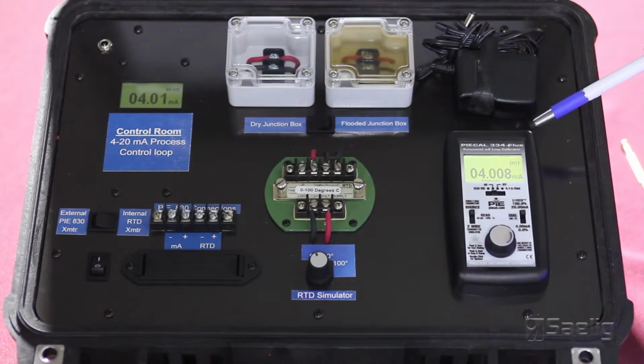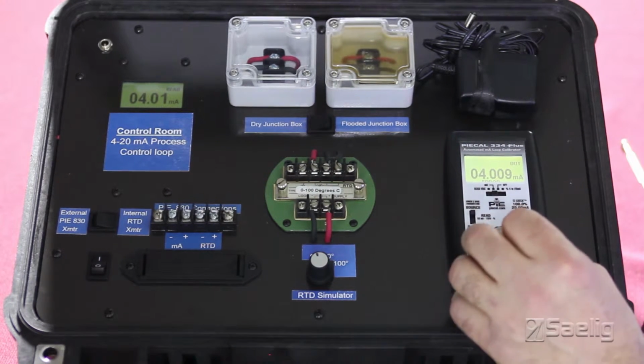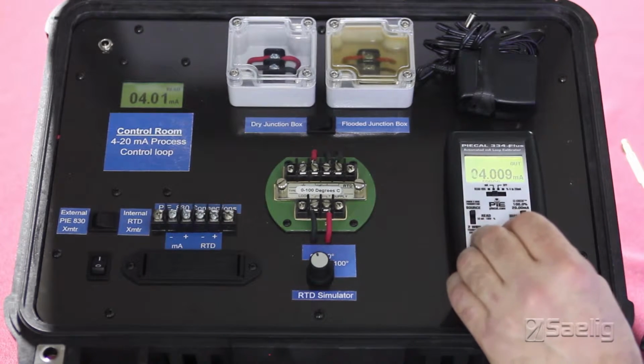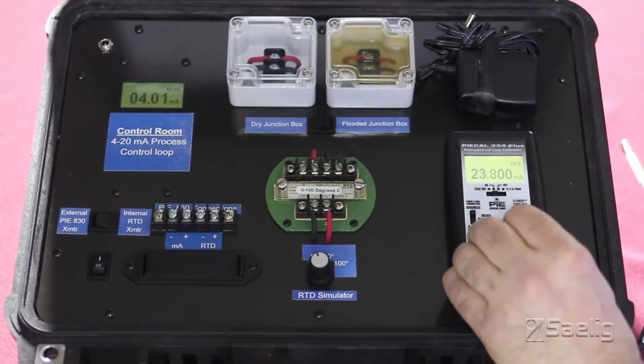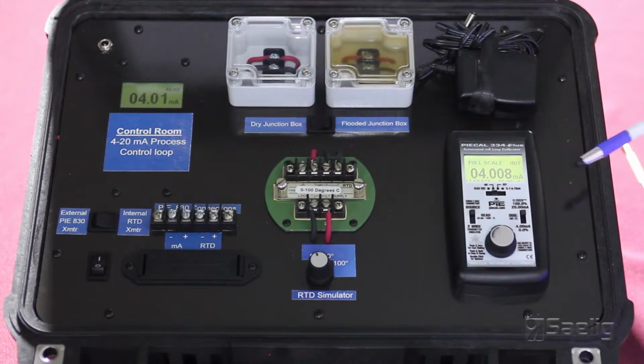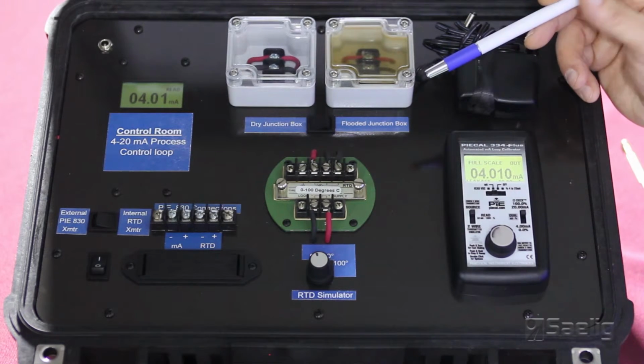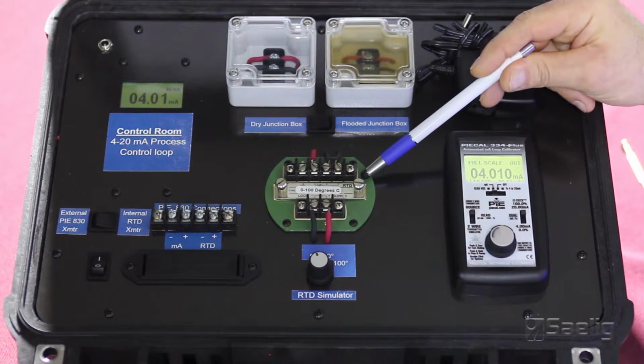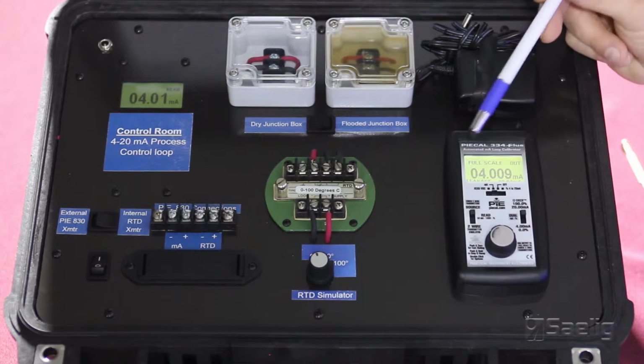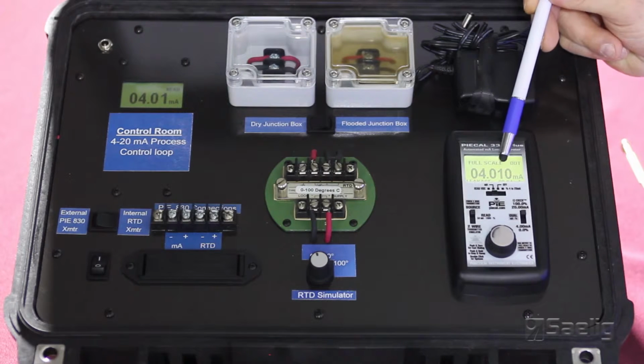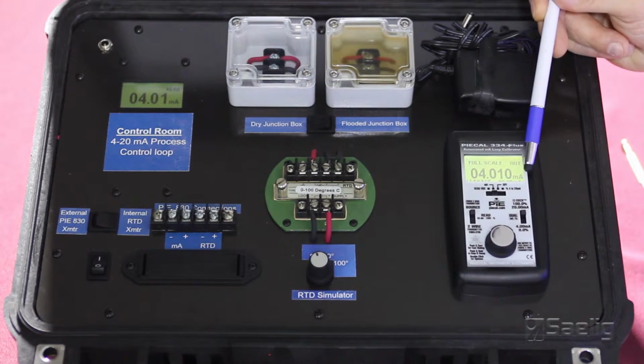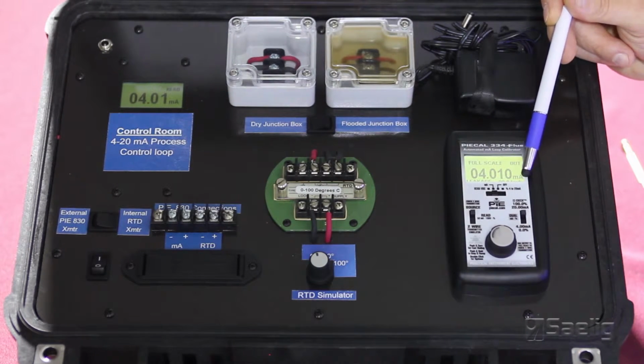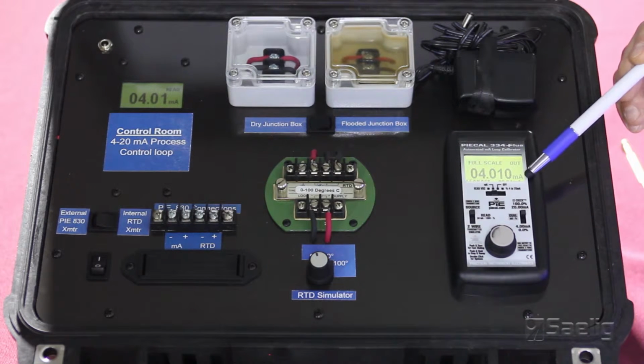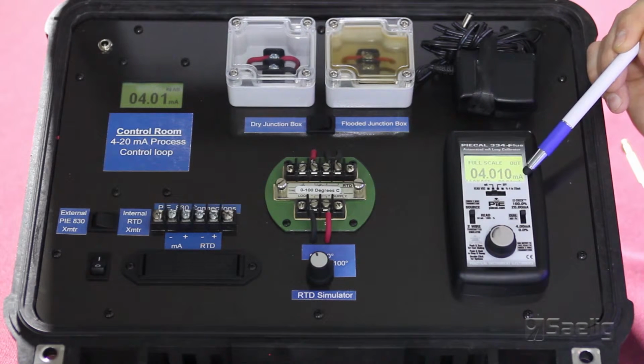The PICAL 334 Plus calibrator will be set with leak detection on and will turn on the power measure mode. Again, this is done by depressing the speed dial and dialing it clockwise to the full position. The calibrator is now powering the loop and simultaneously monitoring the output of our RTD transmitter. As you can see, the output is 4 milliamps. The leakage current in the loop is displayed on the bottom line of the display. And as you can see right now, there is negligible leakage, 0.01 milliamps.